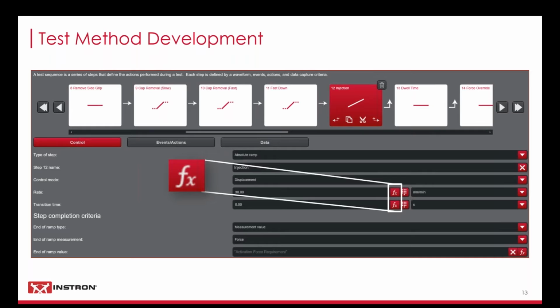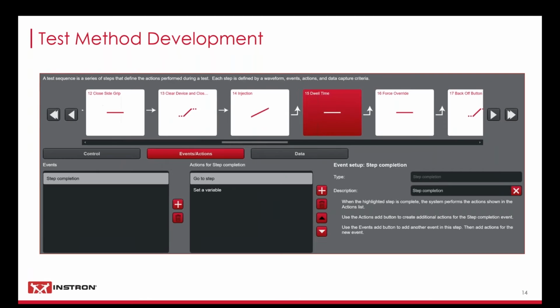This allows users to have these parameters be dependent on user inputs, providing a flexible solution for R&D labs testing many different iterations of a single device design. The events and actions allow for even more intelligence to be built into the system protocol. For example, a user could require an extended dwell time if a minimum expelled volume is not met by the end of the standard dwell time. If the cannula were blocked or bent, for instance, additional time could be needed to expel the full volume. In this instance, the qualitative injection time result would report a failure, alerting the operator to a potential issue.